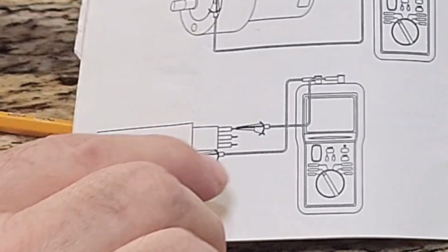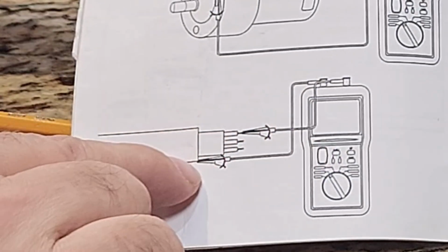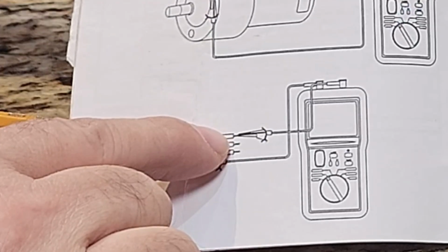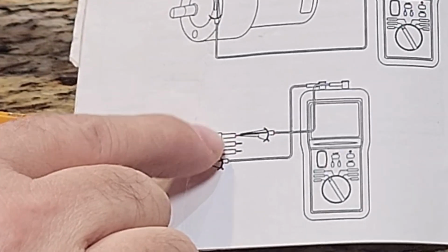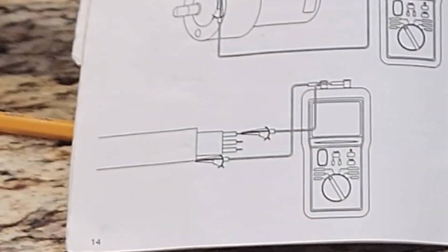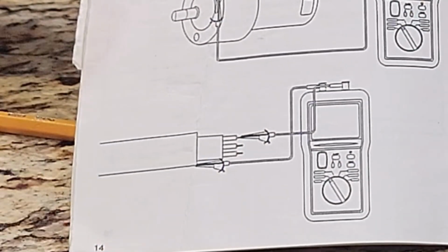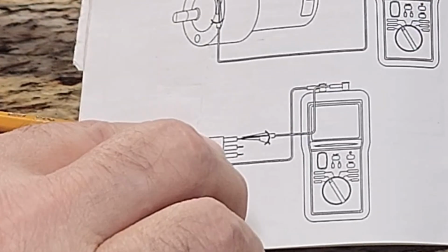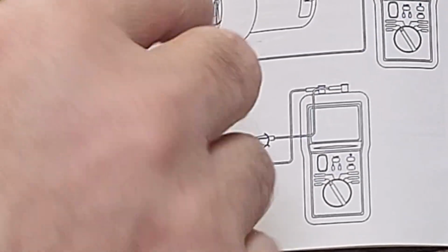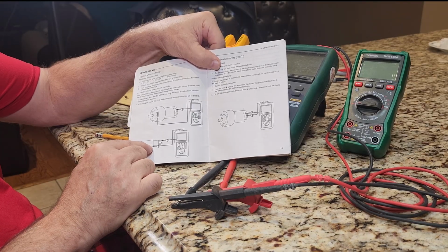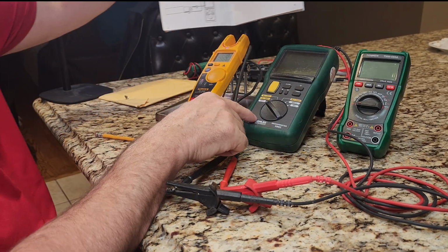So again, the positive side would go to the metal conduit, and then the negative lead goes to each one of the wires. You can do it to the neutral. You can do it to the 3 phases. Because neutral, especially if it's not terminated to the ground yet, you want to be able to determine if there's any connection between one of these phases and ground. That's a perfect example of how, and mostly when, you use it.